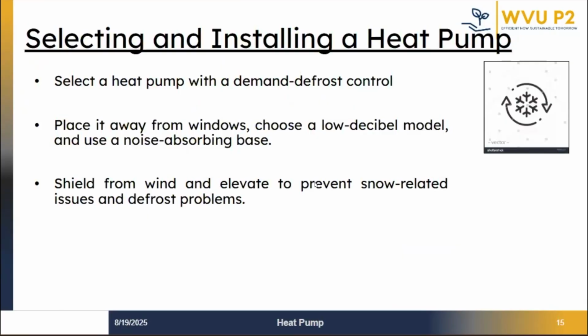So after we know about the heat pump, there should be some criteria for how to select and install heat pumps. The first one is the demand defrost control. Selecting a heat pump with a demand defrost control will minimize defrost cycles, thereby reducing the supplementary and heat pump energy use.